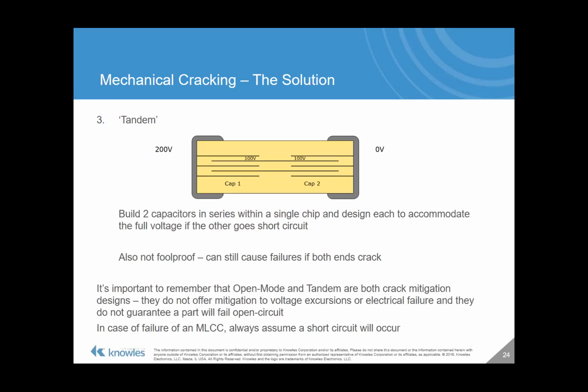The tandem capacitor. Build two capacitors in series within the same unit. The idea here is that each of those capacitors in series is rated to take the full operating voltage of the line. So the example I've shown there is a 200 volt rated part. In actual fact, it's dropping that voltage in 100 volt steps. But they are designed so that if either one of those goes short circuit, the other end can take the full 200 volts.